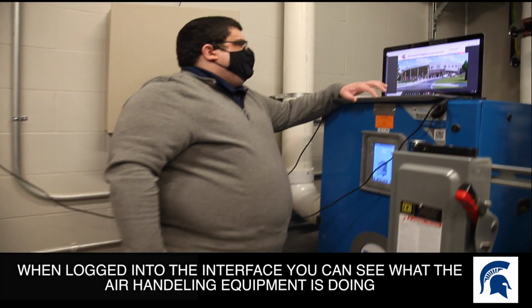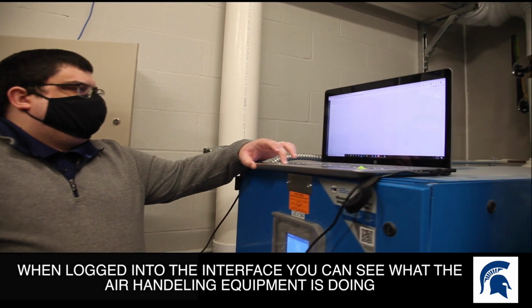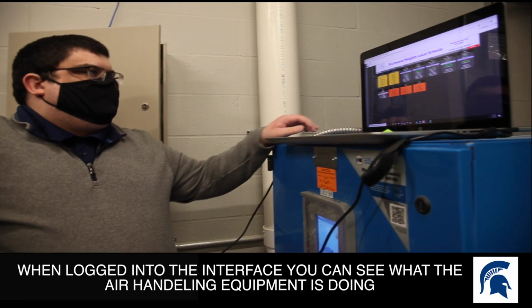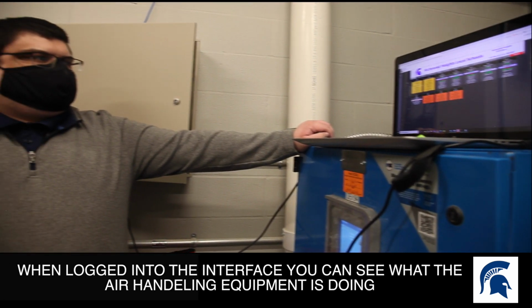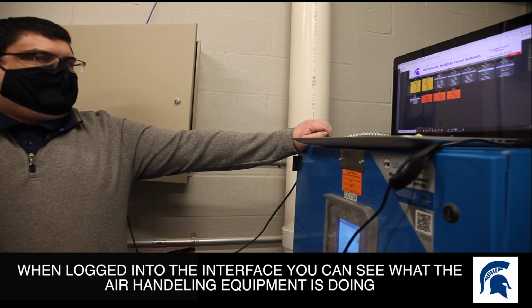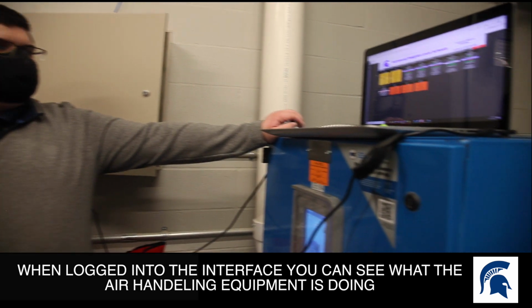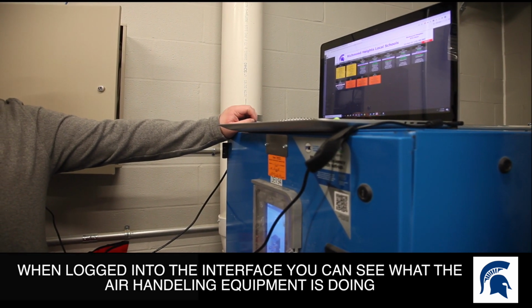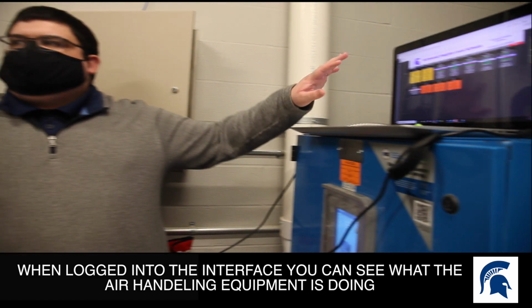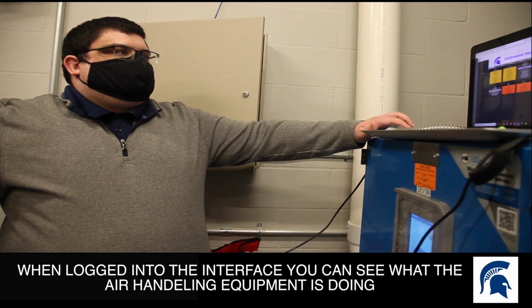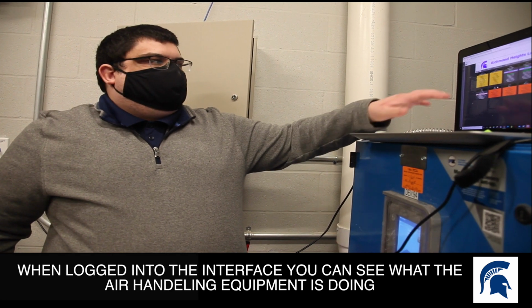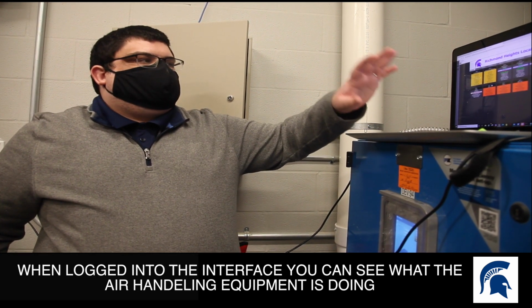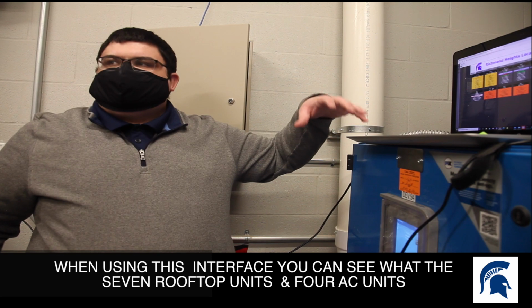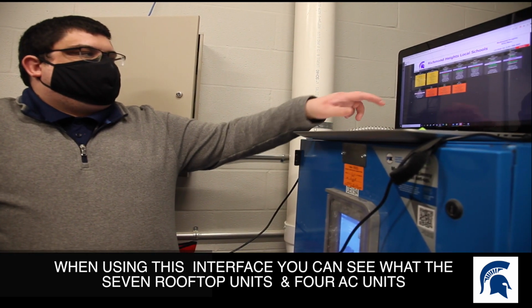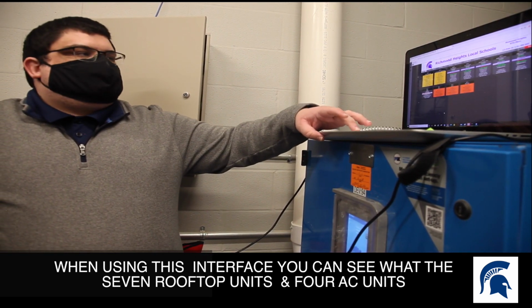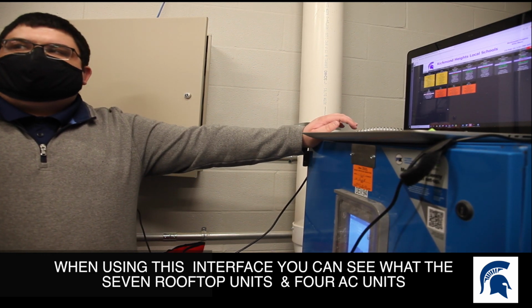So when we're in the system, we can see what the air handling equipment is doing. Right now, we're still working on a couple of little communication problems. That's why you see the yellow and the orange. But you can see on this screen what all 8 of the rooftops are doing. Well, not the library, so the 7 for the school. And then you'll be able to see all 4 of the AC units for the telecom rooms on the screen as well.